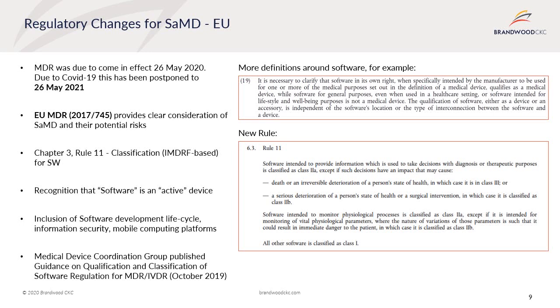The MDR also introduced Rule 11 to classify software as a medical device based on the IMDRF risk classifications and how the information the software provides is used for decisions in relation to diagnosis and therapeutic purposes. Most software previously classed as Class 1 under the MDD are likely to be up-classified to Class 2A or higher. Additional changes include recognition that software is an active device, inclusion of requirements around software development lifecycle, information security, mobile computing platforms, special labelling requirements, specific risk management considerations, and application of UDI for software including for software changes.